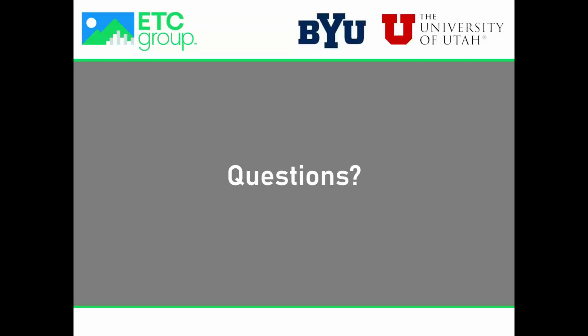There have been lots of instances of connecting that work order system via software like an API, so the two systems can talk to each other. What Jim and Josh are bringing up is really important—if you choose to do that, eMaint is one example we've connected to. The most important thing is don't let it automatically do things; make sure there's human intervention to say, yes, I agree with this fault and I'd like it created into a work order, so you don't get a flood for sure. We've seen that happen, and that intermediate step of allowing or disallowing faults to go through is a really good way to do it. But most people would rather just be in charge of that themselves, so most have chosen not to go with the automatic option. It's possible though.